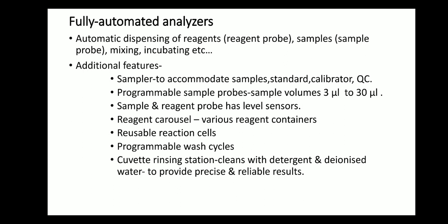Then aspirating the sample, aspirating the reagent, mixing it in a cuvette, then incubation, then displaying the results, printing, everything is done by the fully auto analyzer. So this performs all the things that a semi-auto analyzer does. Additional to that, it has a sampler. What do you mean by sampler? This is a place where it accommodates sample, standard, calibrator and quality control, QC. So everything can be accommodated in that.